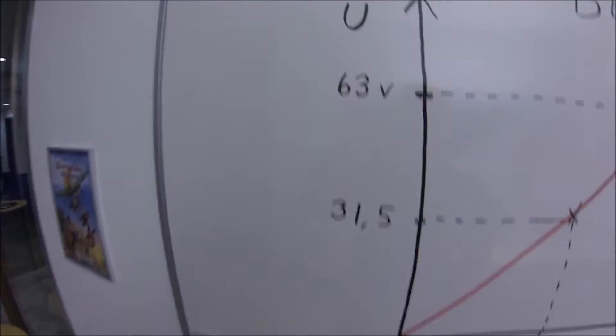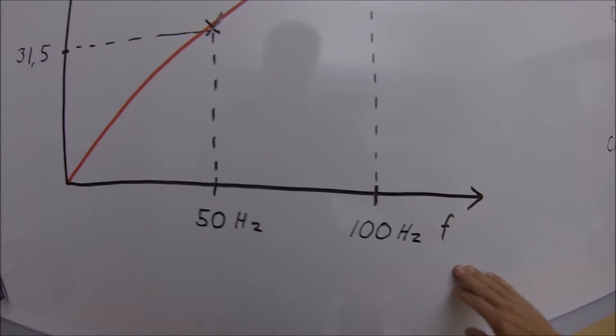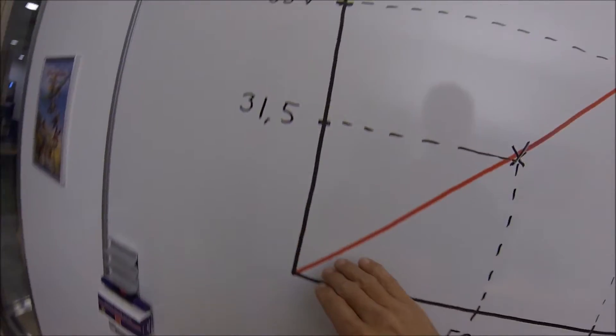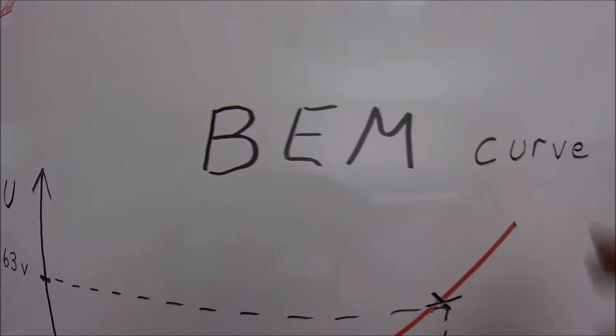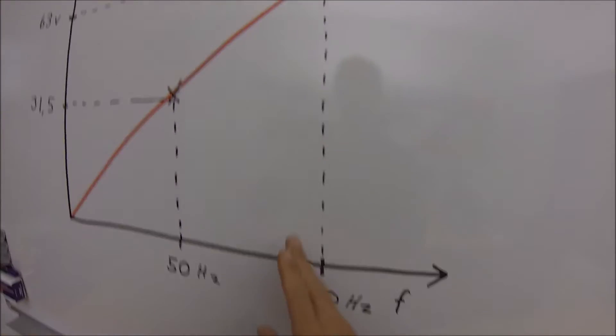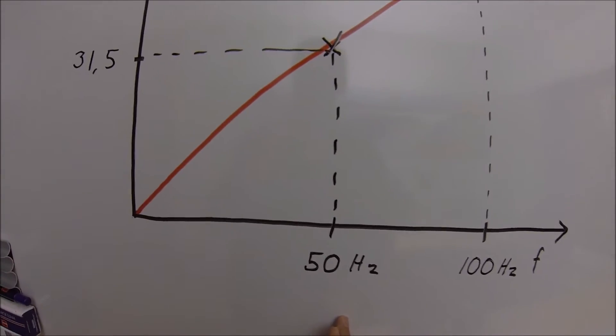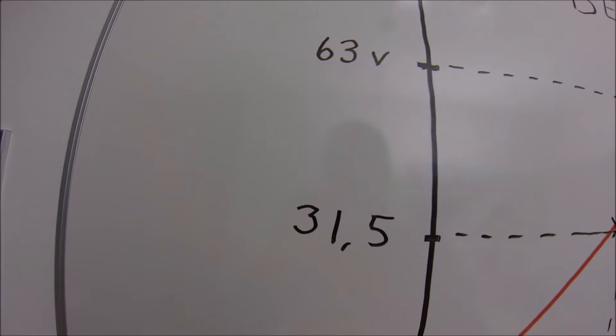The relation between the voltage on the output and the rotation speed of the shaft and then also the frequency is a constant relation called the back EMF curve. At 100 hertz this specific generator produces 63 volts. Half the speed, 50 hertz, it produces also the half voltage.